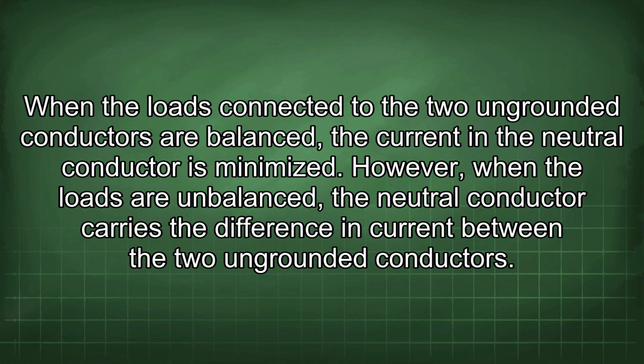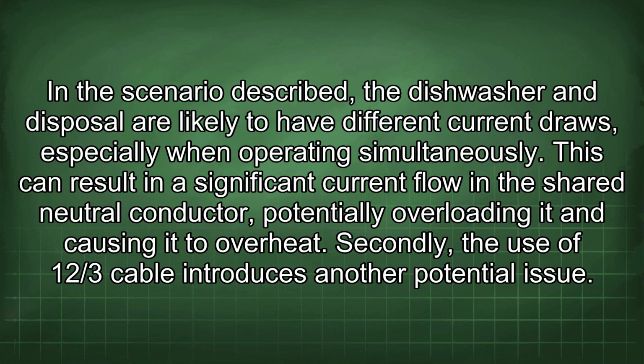When the loads connected to the two ungrounded conductors are balanced, the current in the neutral conductor is minimized. However, when the loads are unbalanced, the neutral conductor carries the difference in current between the two ungrounded conductors. In the scenario described, the dishwasher and disposal are likely to have different current draws, especially when operating simultaneously. This can result in a significant current flow in the shared neutral conductor, potentially overloading it and causing it to overheat.